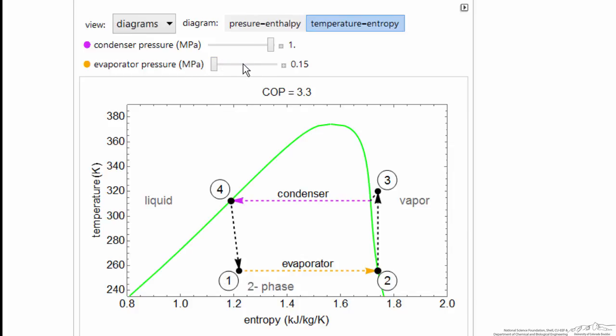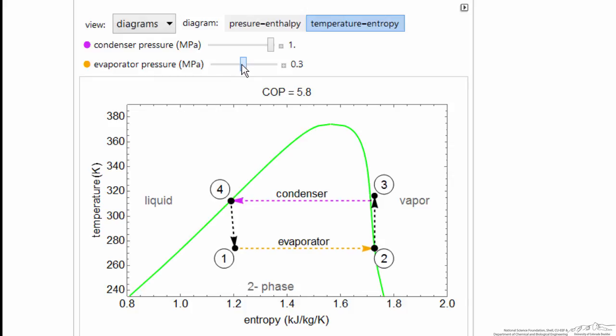We can change the behavior and pressure. If we raise this evaporator pressure, we raise the temperature so we are not getting as cold, but our coefficient of performance goes up if we are not getting as cold.